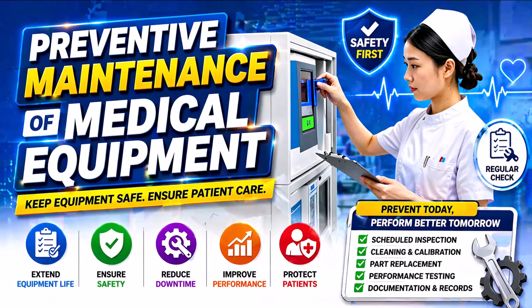Electrical safety testing is another critical part of preventive maintenance. This includes checking grounding continuity, insulation resistance, and leakage current. These tests are essential to prevent electrical shock hazards to patients and healthcare staff. Specialized electrical safety analyzers are commonly used for this purpose.